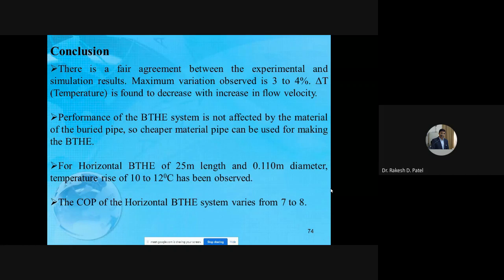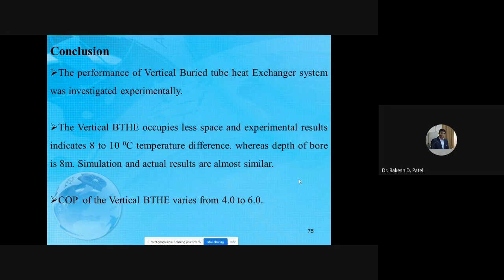For the horizontal heat exchanger of 25 meter length and 0.110 meter diameter, a temperature rise of 10 to 12 degrees centigrade has been observed. The COP of the horizontal system varies from 7 to 8. The performance of the vertical buried tube heat exchanger was investigated experimentally, and the vertical heat exchanger occupied less space compared to the horizontal. Experimental results indicate an 8 to 10 degrees centigrade temperature difference, where the depth of the bore is 8 meter.